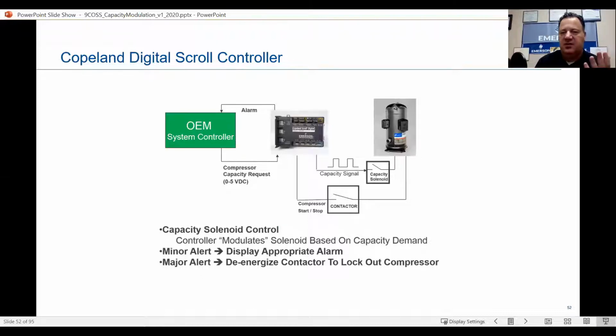So if it's calling for 50% in refrigeration, we've got that coming in, and it's telling it 10 seconds loaded, 10 seconds unloaded, and so on and so forth. We're coming out of the contactor, the compressor start, stop, back to the IDCM. If we get an alarm, it comes back to our controller. The capacity solenoid control modulates the solenoid based on capacity demand. A minor alert will display the appropriate alarm. A major alert de-energizes the contactor to lock out the compressor.